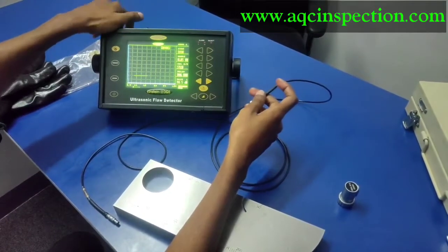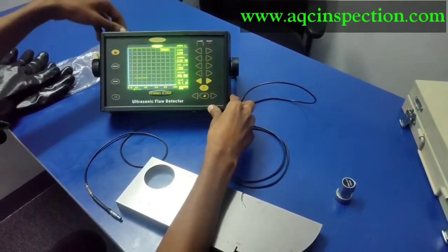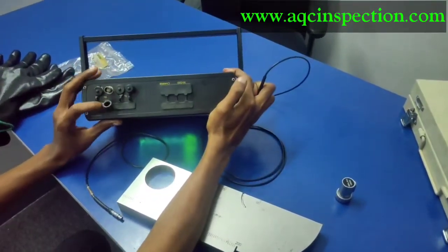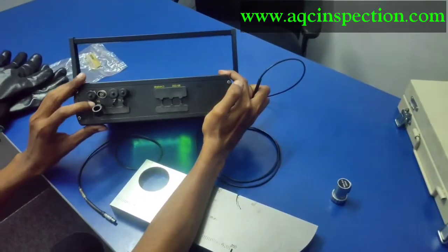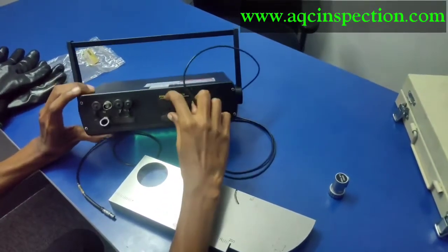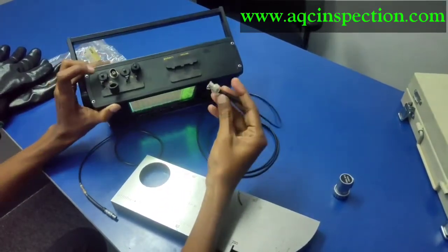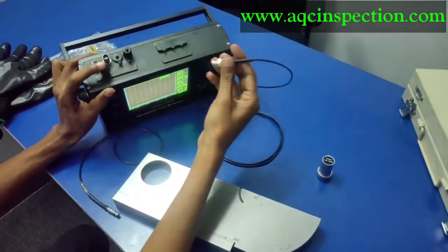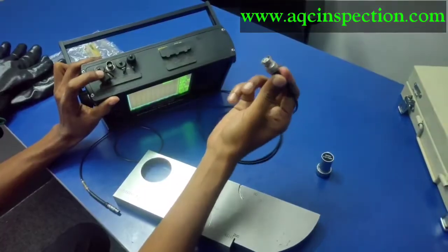First, we are going to connect the probe using a BNC connector and a LEMO cable. We have two ports right here, one is for the transmission, one is for the receiving, and here it's a charging port. Since we are using a normal probe, we can use a single wire which acts as a transmitter as well as a receiver.